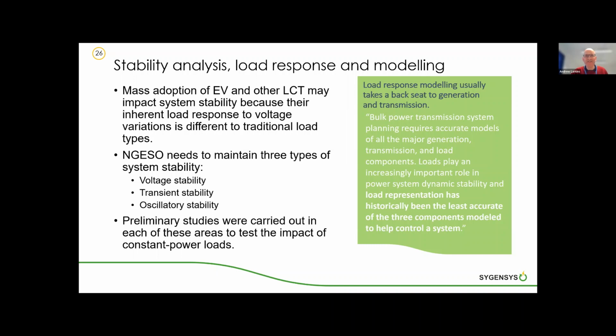Now, ESO needs to maintain three types of system stability: voltage, transient, and oscillatory. We'll consider each of those. We carried out some very preliminary studies in each of those areas to test the impact of constant power loads. This quotation on the right here is from a US document on the Department of Energy website. It says, bulk power transmission system planning requires accurate models of all three components: generation, transmission, and load. But historically, most of the focus has been on generation and transmission, and load modeling has effectively taken a bit of a backseat.